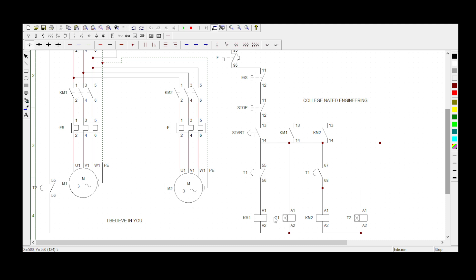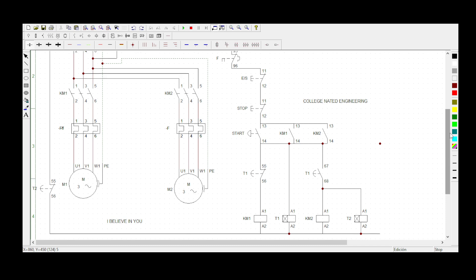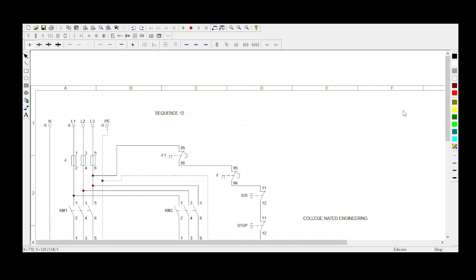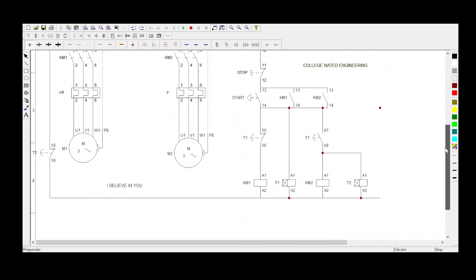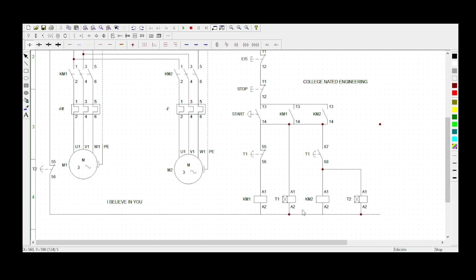What stops Motor 1 from rotating is this normally closed contact of Timer 1 — after 10 seconds when Timer 1 has been energized, it becomes normally open to stop Motor 1, and here normally closed to start Motor 2. When Motor 2 starts, Timer 2 also starts, which is a delay-on timer. After 10 seconds, this normally closed becomes normally open on the line going to neutral, because for a coil to be energized it needs to receive power from both A1 and A2.